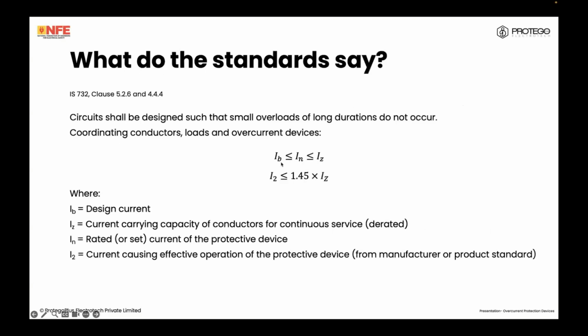And then the cardinal requirement: IB shall be lesser than or equal to IN shall be lesser than or equal to IZ. This is interesting. Very common, I've heard electricians say, if you have a certain load, we put a certain cable. Say 13 ampere load, we'll just take a cable that can say take 20 amperes. Safe. Absolutely not safe. You're forgetting about the breaker, which is this IN. IB shall definitely be lesser than or equal to IZ. IZ should definitely be greater than or equal to IB.